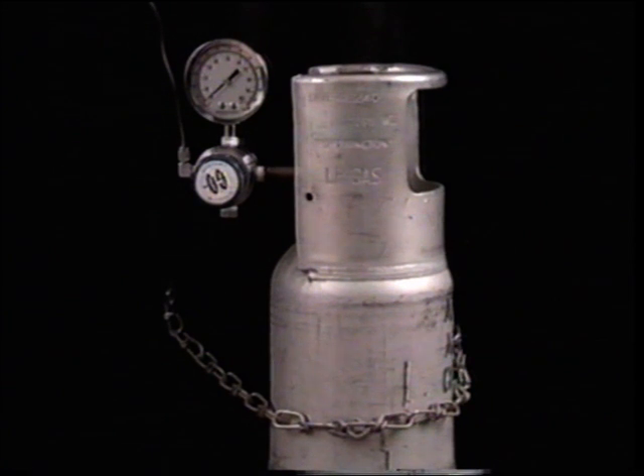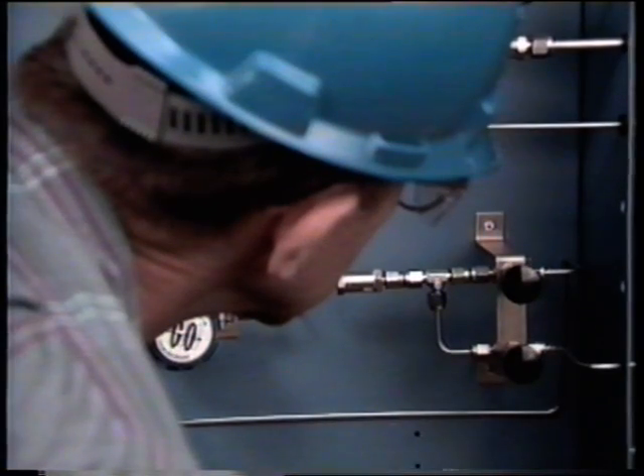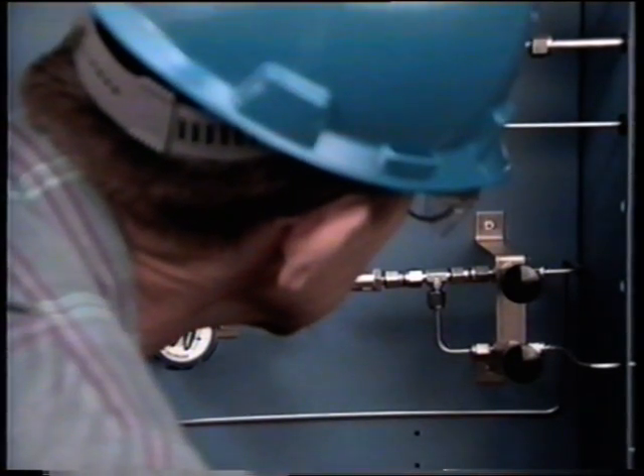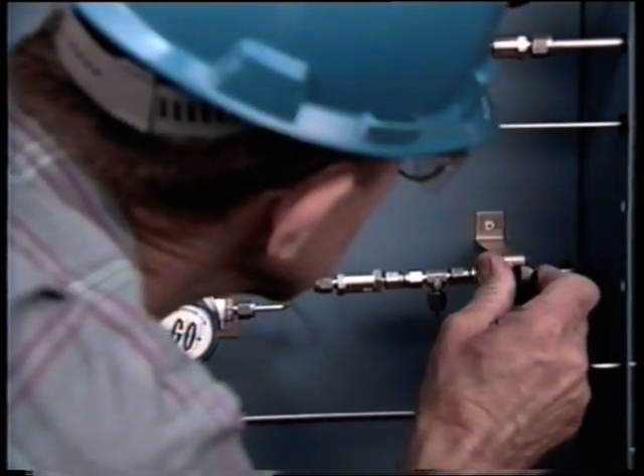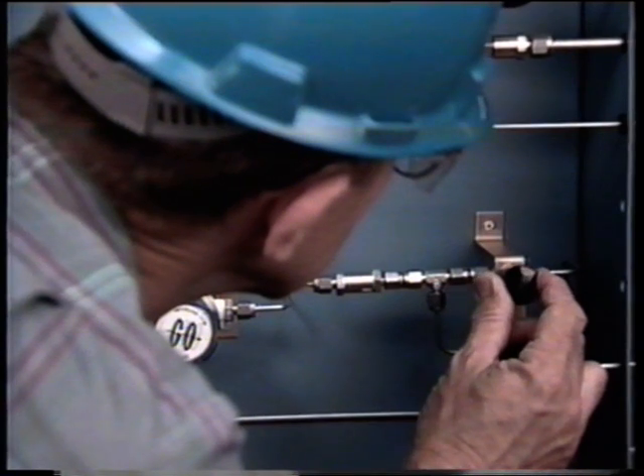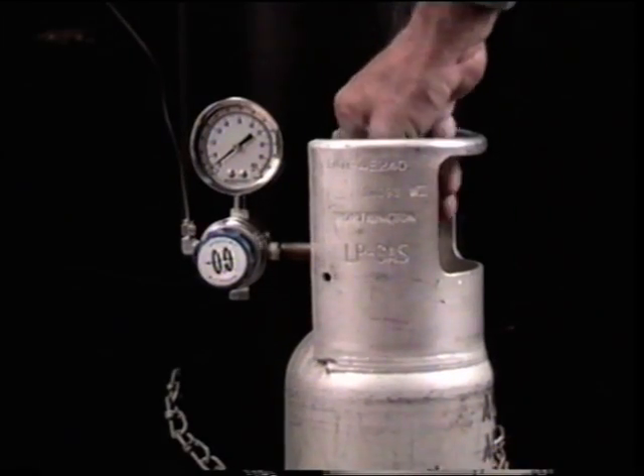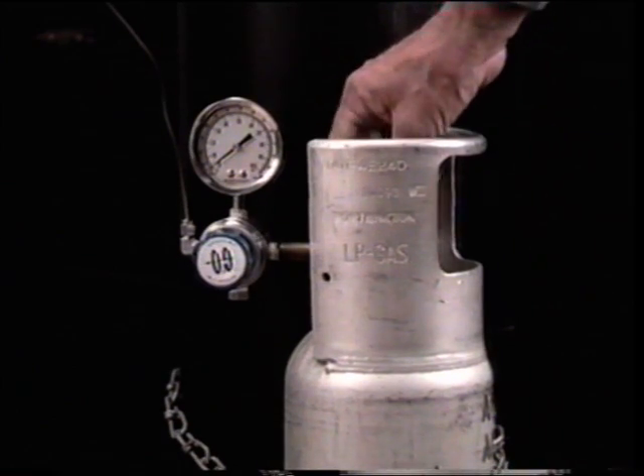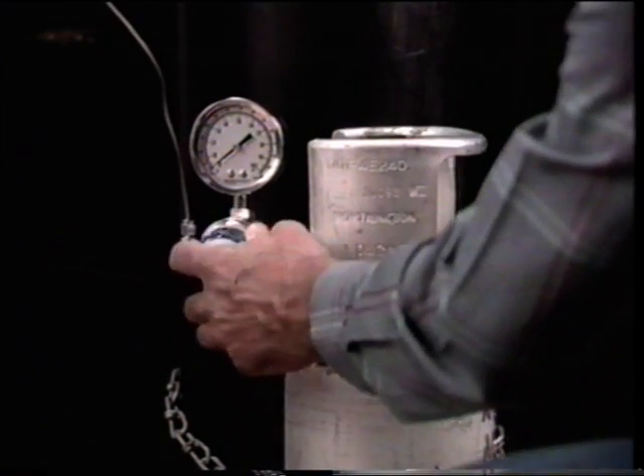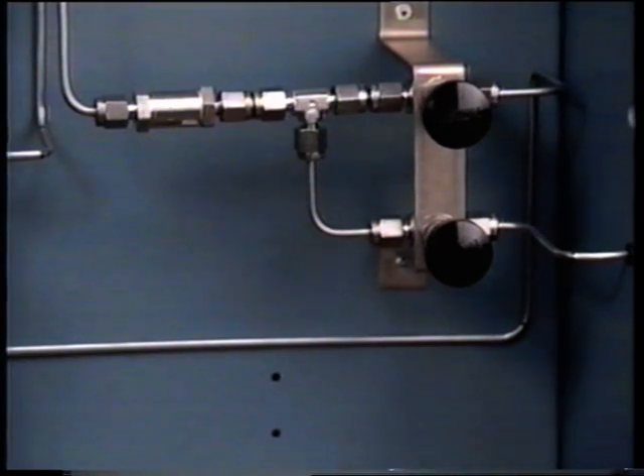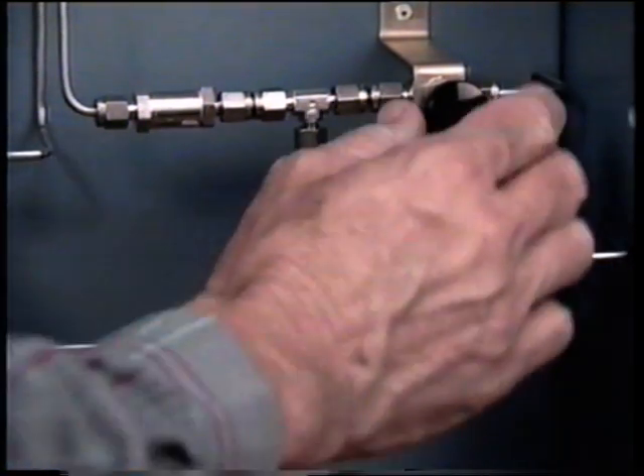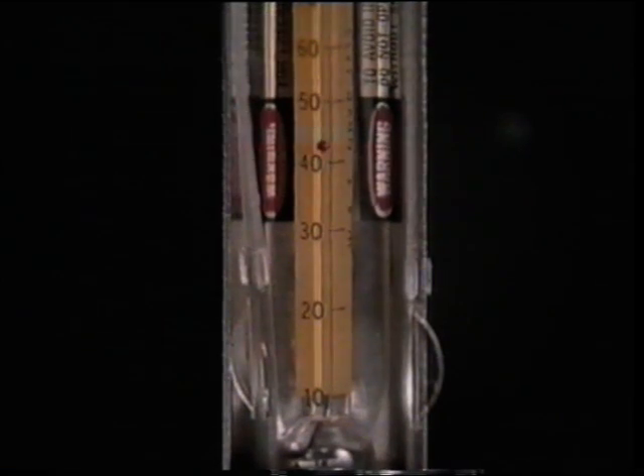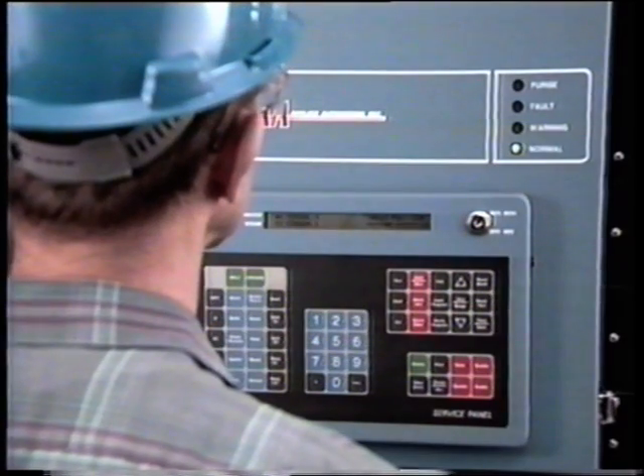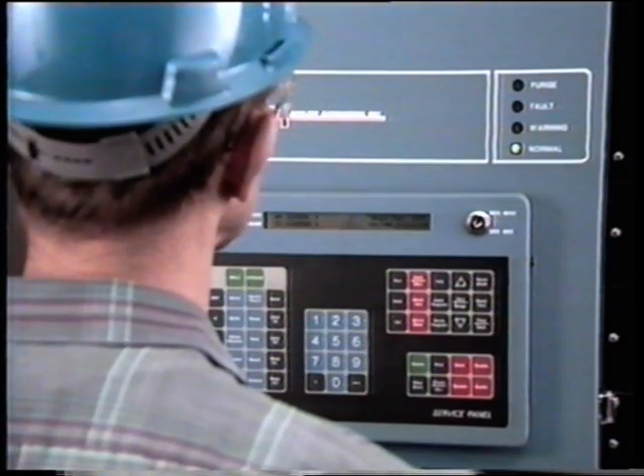To manually calibrate this gas chromatograph, you'll use a standard calibration sample tank. First, be sure that you are familiar with the location of the analyzer's valves and rotometers. Close the Calibrate Standard Flow Control valve. Open the shutoff valve on the Calibrate sample tank and set sample pressure according to specifications. Close the analyzer's sample flow control valve. Adjust the Calibrate Standard Flow Control valve until the analyzer's sample flow rotometer is at the level specified by the manufacturer's guidelines. Now, you're ready to calibrate the chromatograph.